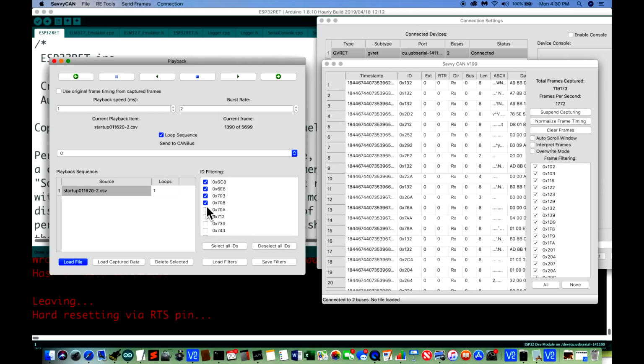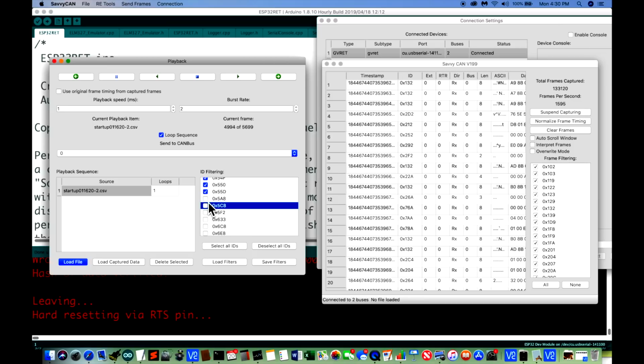So I'm gradually eliminating messages out of this loop, and I'm going to keep doing that until we find a message that causes the contactors to close. If I turn one message off, or maybe more, then we're not going to close the contactors after all.